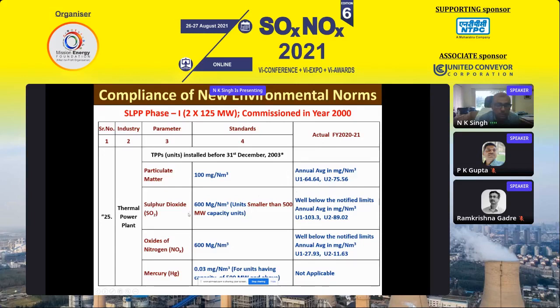Similarly, for sulfur dioxide, the norm is 600 mg/Nm³. Our emission is 103.3 and 89.02. And I would like to tell the audience, we are using low grade lime, having 40-41% CaO content and 70% CaCO3. Even though, we are able to meet the requirements. Though it has some issues on the operational side, there is slagging, there is an issue of choking of the superheaters, but we are fully meeting the norms. Then the oxides of nitrogen, it is limited to 600 mg/Nm³, whereas we are meeting it in unit 1 and 2 both. If you see, it is less than 30.